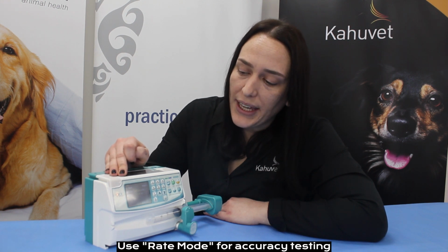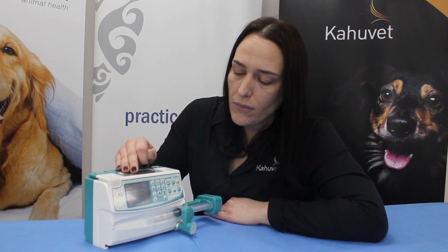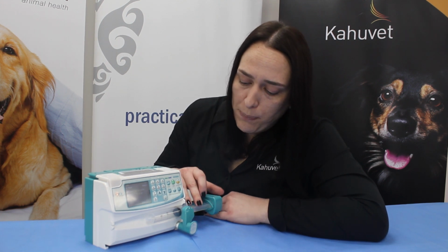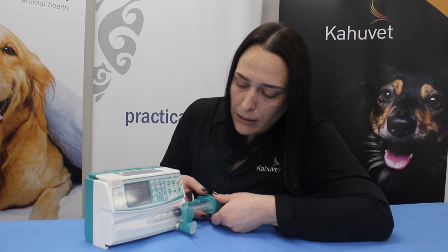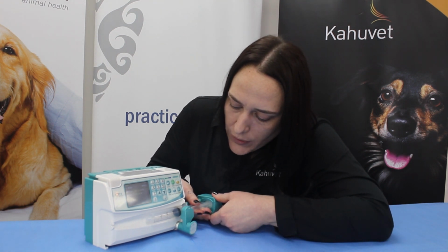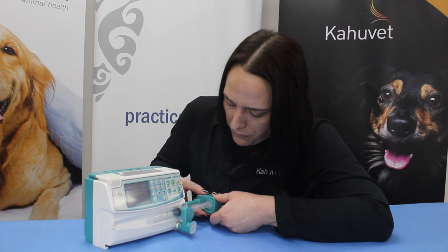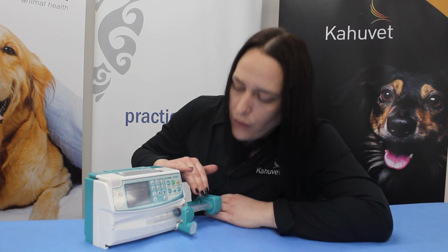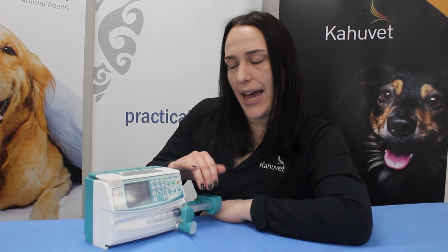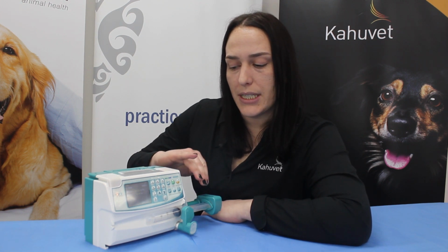The important one here is our volume to be infused. That we've set as a total of 10 mils. On our syringe, we've drawn back to our 20 mil mark, and we're going to make sure that's nicely on the line there for 20 mils. And the reason we're drawing back to 20 mils here and doing the volume to be infused as 10 is we want to be able to see if there's any discrepancy on the syringe. So it will give it the ability to go above or beyond that 10 mil mark, so we can see if there is a major discrepancy.